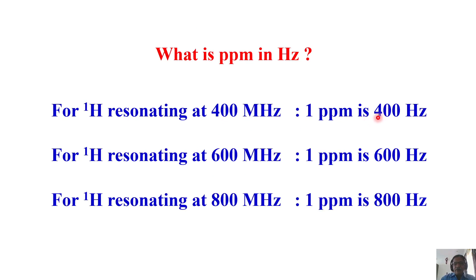So now we will try to understand what a ppm is and what a frequency is. What is ppm in hertz? Just now we saw that for the resonating frequency of a proton in a 400 megahertz spectrometer, 1 ppm is 400 hertz. Please remember, we just calculated that 1 ppm is 400 hertz. Similarly at 600 megahertz, 1 ppm is 600 hertz. In an 800 megahertz spectrometer, 1 ppm is 800 hertz. Very easy. When you want to express ppm in hertz, simply take the resonating frequency of that spectrometer. For example, at 400 megahertz, 1 ppm is 400 hertz; at 600 megahertz, 1 ppm is 600 hertz.